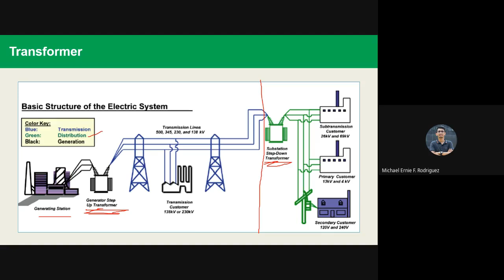Take note, the green part is distribution. This part is distribution. The first transformation takes place at the distribution substation, where incoming transmission line voltages are stepped down to primary feeder voltage. For example, you have 138 kilovolts, and you step that down to 13.8 kilovolts or 13.2 kilovolts.